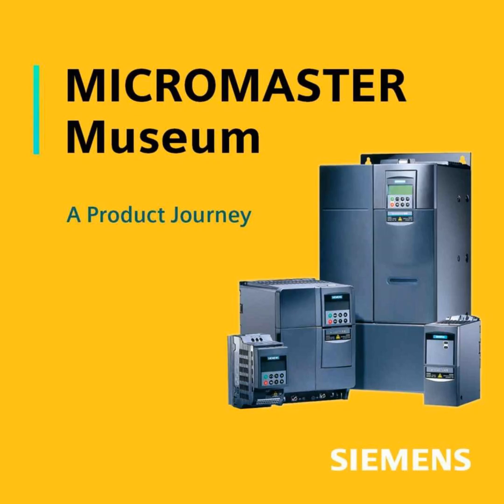They got into the inverter room, and inverters are really interesting things because they're a computer and they're a series of high voltage switches. And if these little strands were able to get where there were big volts and bridge over to where there were only supposed to be little volts, there was a bit of a flash and the thing stopped working. And that was a painful exercise where we learnt about the values of coating circuit boards, which we do in the factory today.